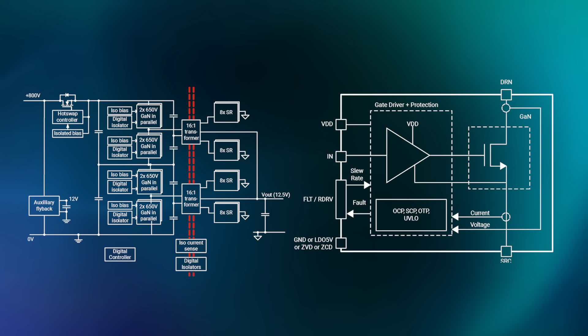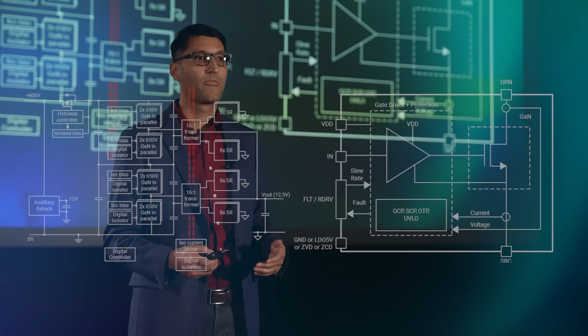These IBCs are operated essentially as a DC transformer with an unregulated output, so for 800 volts in and 12 volts out, it has effectively a 64:1 conversion ratio. We can smartly design the converter topology by connecting two converters with a series input and a parallel output.